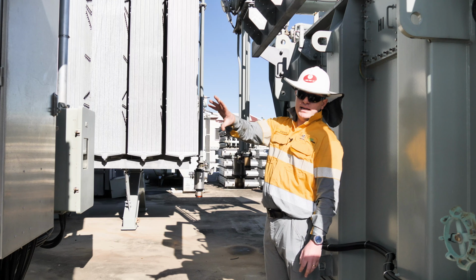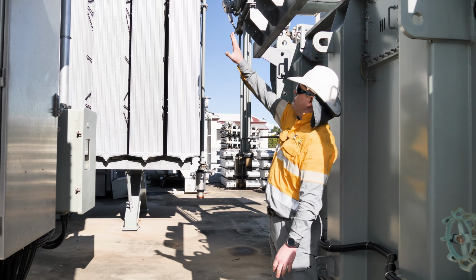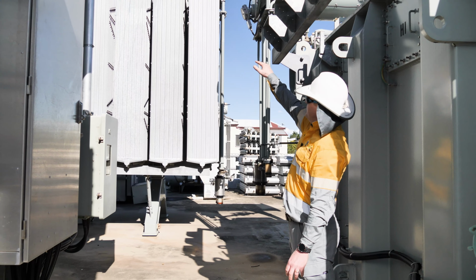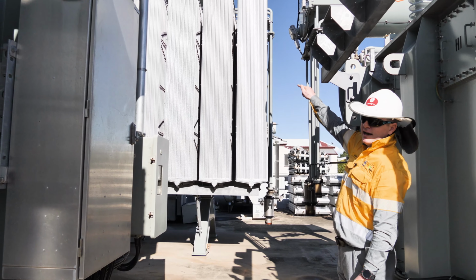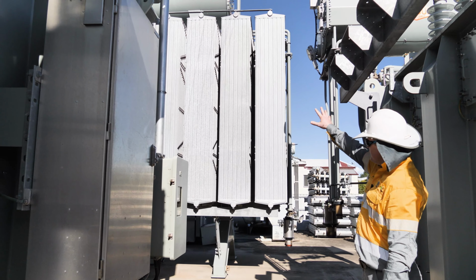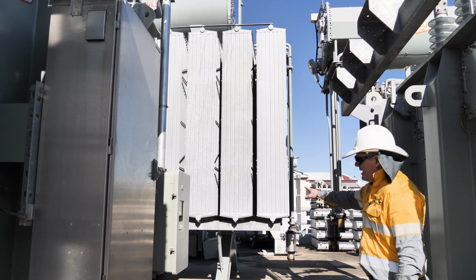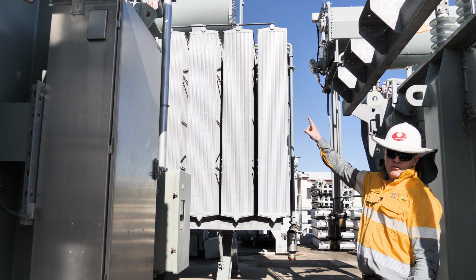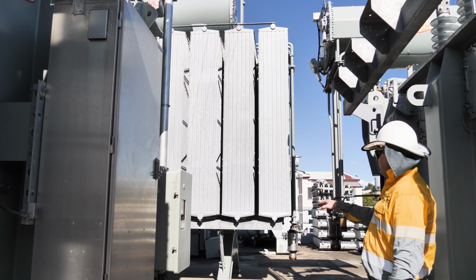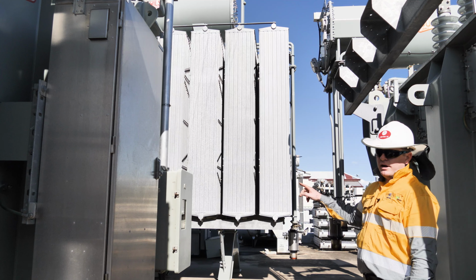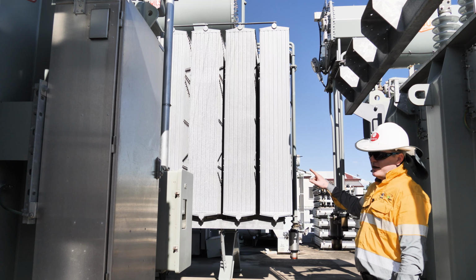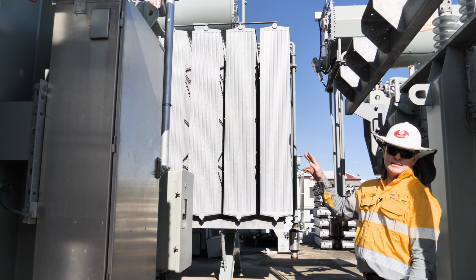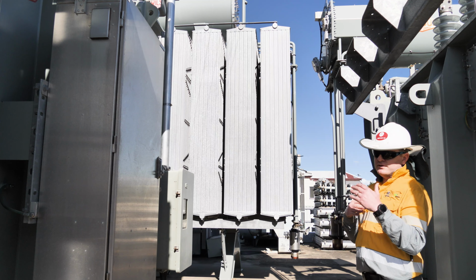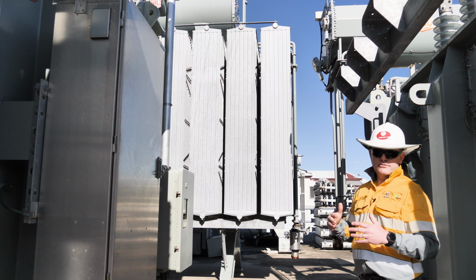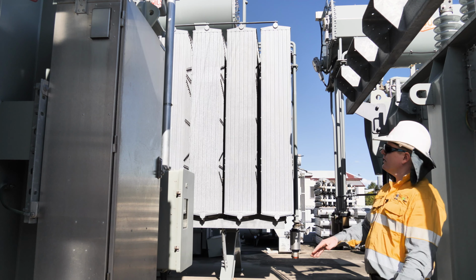Once it gets hot in the tank, the oil rises, goes through the pipework, and comes in at the top of the radiators. It falls. As it falls, it cools, and it gets pumped back into the transformer to create a circuit. By pumping the oil, we can get a higher rating out of the transformer because we have more cooler oil coming into the system, and we're able to keep those windings at a cooler temperature for increased power flow.